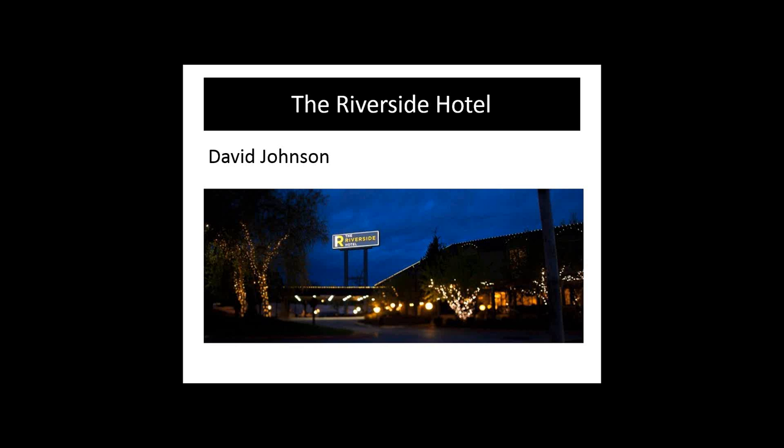And then there's no insulation on the top of the second floor. It's a two-story building, and each of those rooms is duplicated above it with a matching room. The second-story ceiling doesn't really have any insulation, which we finally determined was because you didn't want to freeze the fire sprinklers, which had been added. So that was a long discussion to figure out how to do that, and we have not fixed that yet, because if we put in insulation, we'll probably cause our sprinklers to freeze. We've got five or six different ideas of how to handle that, but it has not reached the stage where we want to spend that money.